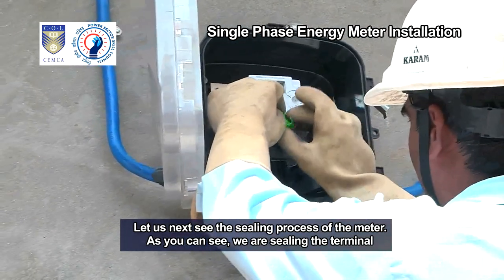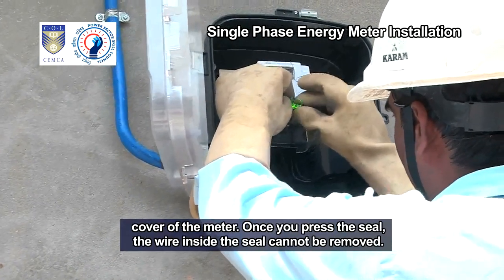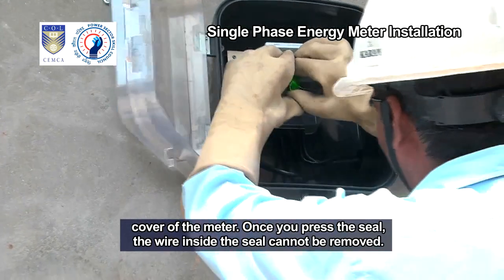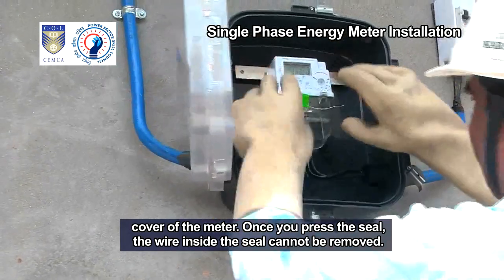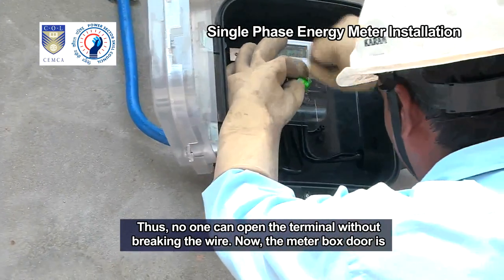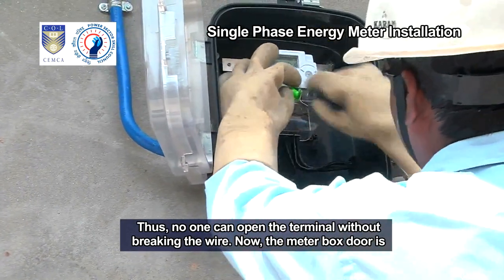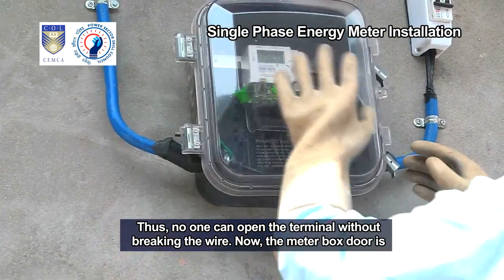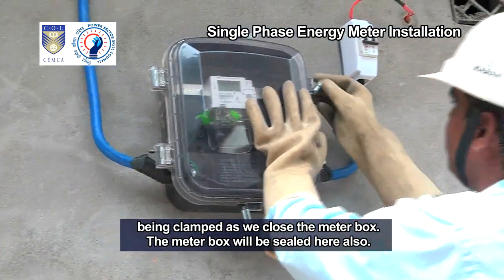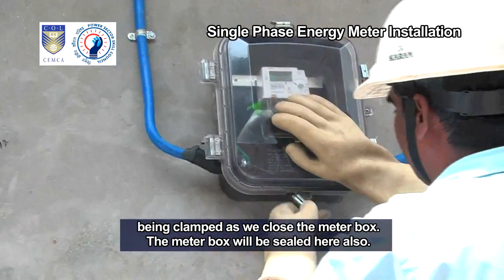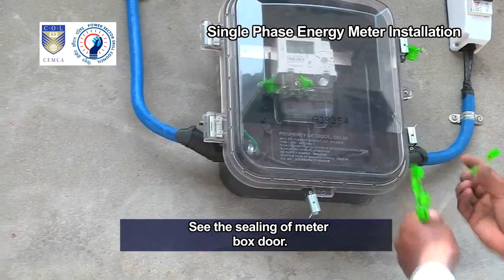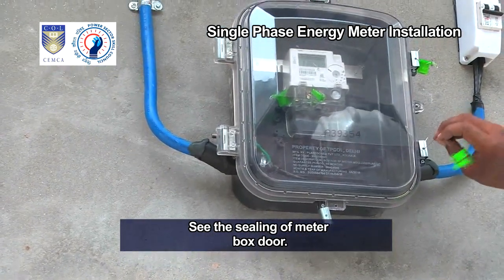As you can see, we are sealing the terminal cover of the meter. Once you press the seal, the wire inside the seal cannot be removed. Thus, no one can open the terminal without breaking the wire. Now, the meter box door is being clamped as we close the meter box. The meter box will be sealed here also. See the sealing of the meter box door.